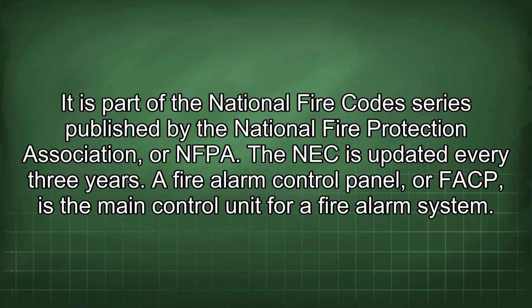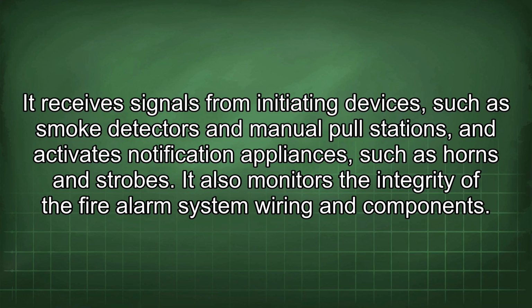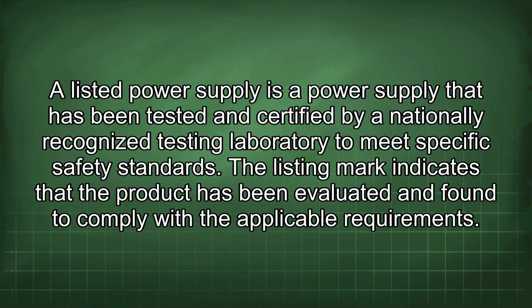A fire alarm control panel, or FACP, is the main control unit for a fire alarm system. It receives signals from initiating devices such as smoke detectors and manual pull stations and activates notification appliances such as horns and strobes. It also monitors the integrity of the fire alarm system wiring and components. A listed power supply is a power supply that has been tested and certified by a nationally recognized testing laboratory to meet specific safety standards. The listing mark indicates that a product has been evaluated and found to comply with the applicable requirements.